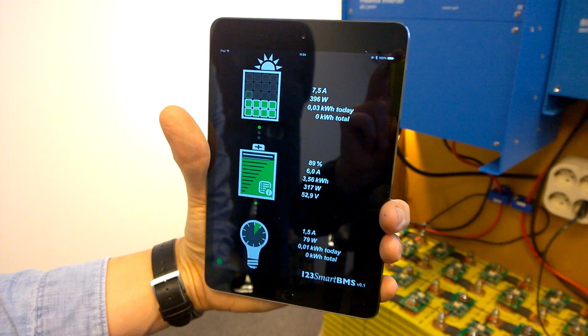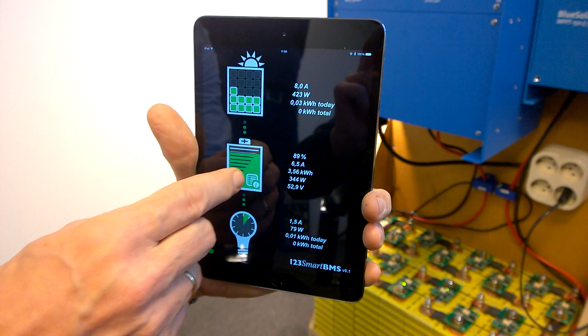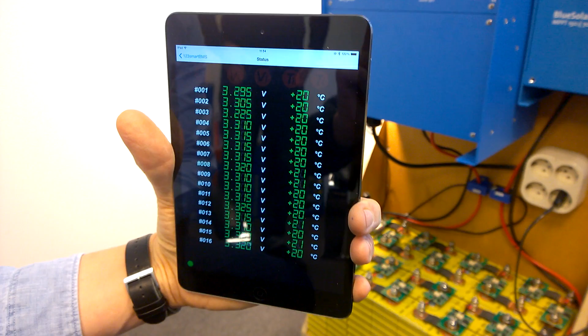Now, going back to this screen, the situation hasn't changed much, but if I'd like to know the individual cell voltage of each cell, you see it is scanned all the time, and all the cell voltages and temperatures are within safe limits. Were that not the case, one of the relays I showed earlier would switch off, disconnecting the charging or the inverter.